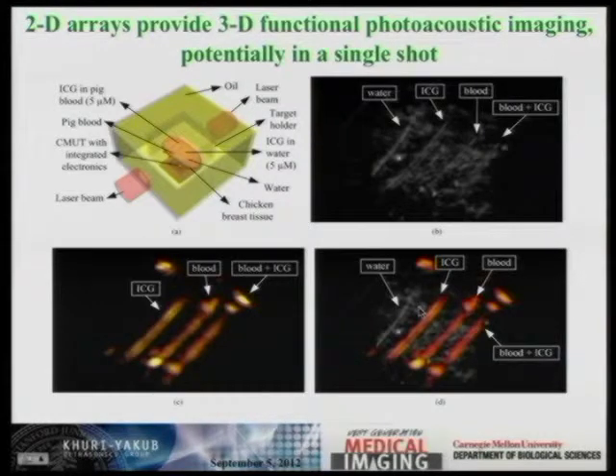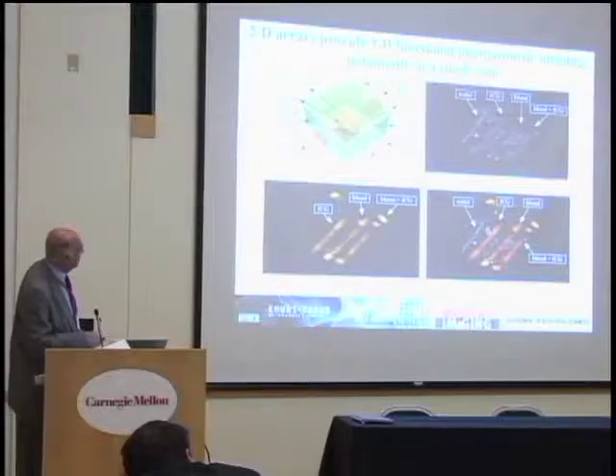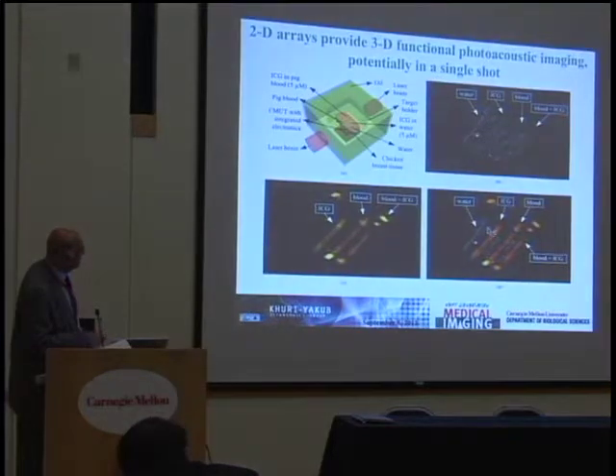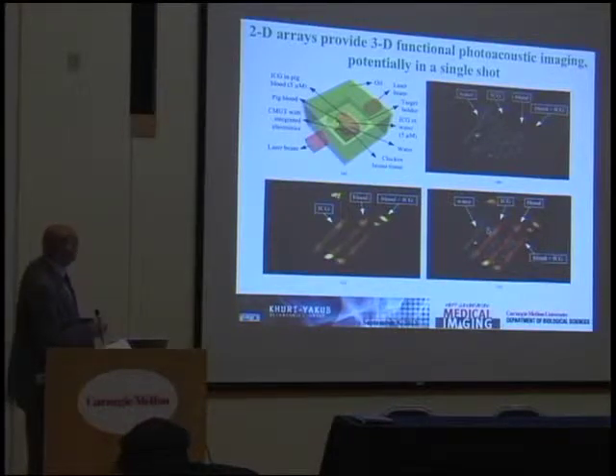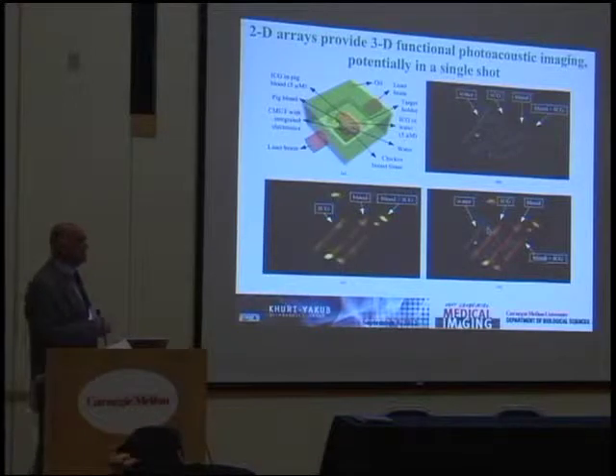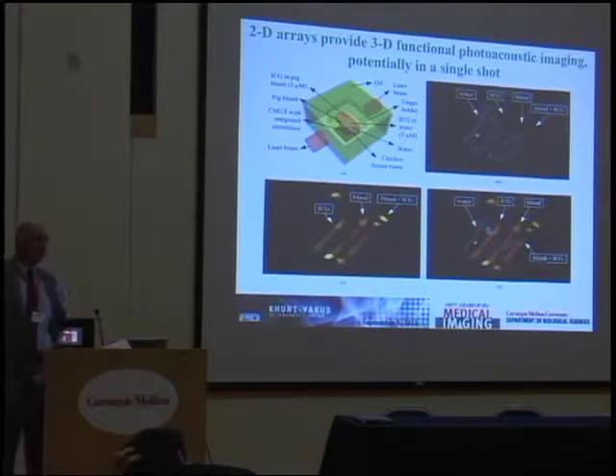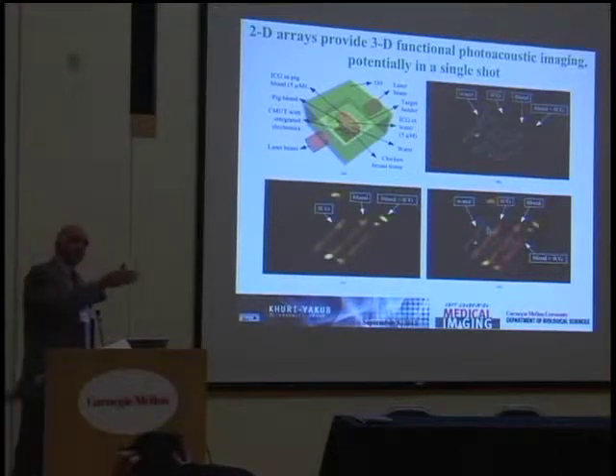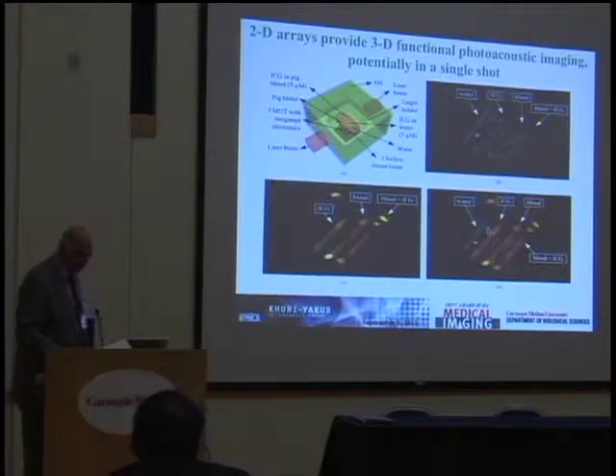Here we have a 16 by 16 2D array. We place it over a phantom with a number of tubes containing different materials — water, ICG, blood, and blood plus ICG. With anatomic imaging you see all 4 tubes, but with photoacoustic imaging you only see the ones with contrast agents: ICG, blood, and blood plus ICG. Also, these tubes were 5 centimeters from the light and 5 centimeters from the array itself, so we're looking at 5 centimeter penetration of light with absorption and scattering, then 5 centimeter propagation to the 2D array.